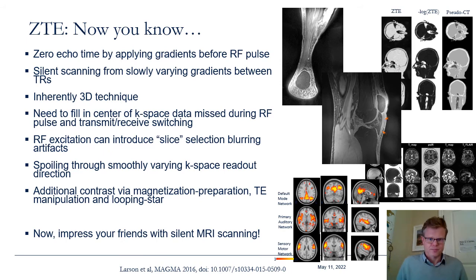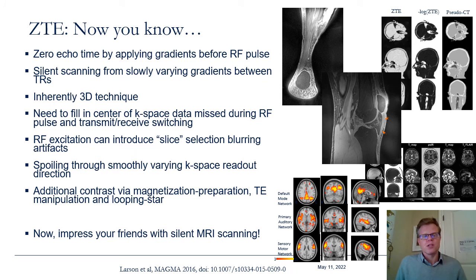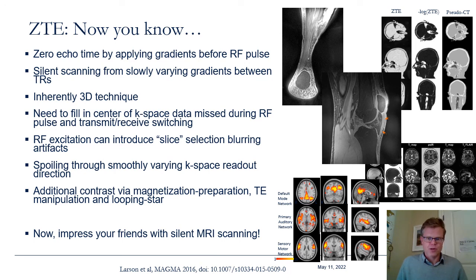In summary: ZTE is achieved by applying gradients before the RF pulse. Silent scanning is enabled by slowly varying gradients between TRs. It is inherently 3D and requires filling the center of k-space. Care must be taken with RF excitation to avoid slice-selection blurring artifacts, addressed through design parameter choices or advanced tricks. Spoiling is achieved through smoothly varying k-space readout directions. Additional contrast dimensions are opened up by magnetization preparation, TE manipulation, and the looping star approach. Thanks for listening — now go impress your friends with your silent MRI scanning knowledge!